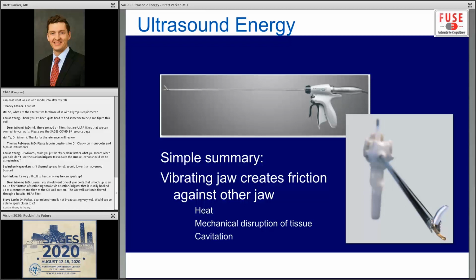So the heat, as we previously mentioned, is basically caused by friction, and ultrasonic instruments can achieve thermocoagulation. The ultimate tissue effect of this thermocoagulation is similar to the electrosurgical devices that we've already gone over with dehydration and protein coagulation. However, the mechanism that causes the temperature in the tissue to rise is different. With ultrasonic instruments, the tissue is heated with extracellular mechanical forces. Think of rapid massage of the tissue. With electrosurgery, the temperature elevation more occurs on an intracellular level with oscillation of intracellular ions.